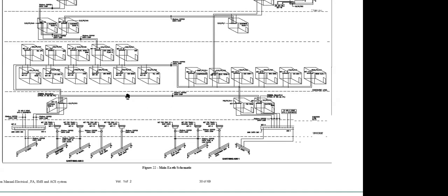And for example, these two strips are creating a bus sort of thing. Generally for building application, or I would say this type of non-infra application, we provide this main earth terminal above the MCC panel, where the earth strips are coming from plate earthing or pipe earthing, and it is connected there. From there to that earth bus, it is going to each and every equipment, and it is a loop.